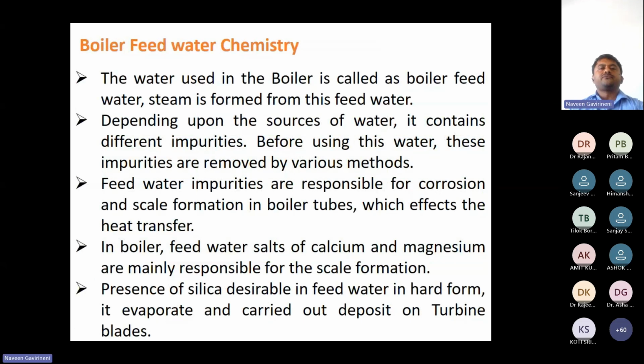So the second one is feed water chemistry. As I explained, feed water chemistry is the most important factor, as the boiler life depends on it. Why? Because if it is not good, we will get corrosion and damage to the tubes and other parts. Whatever happens, happens. So this is the feed water chemistry.